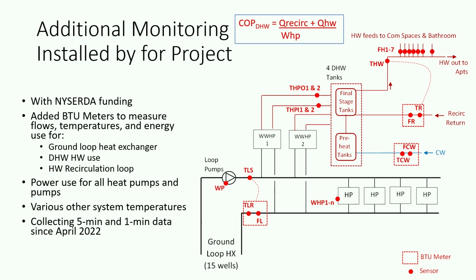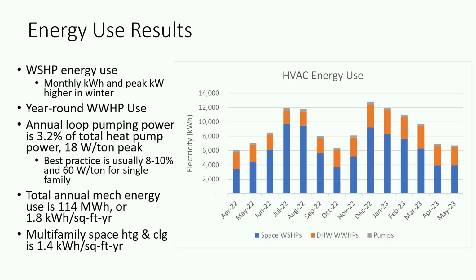I will point out this, obviously, so when I'm going to talk about COP, I'm going to mostly talk about the gross COP of the system, meaning the energy content of what's provided, the recirculation losses, and then I divide by the power use of the heat pump. I call that the gross COP or the plant COP, which is what you can compare to boiler efficiency, for instance. I'll also talk about the net COP, but that'll be different.